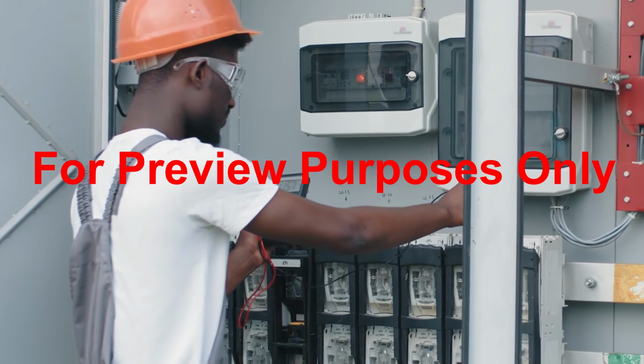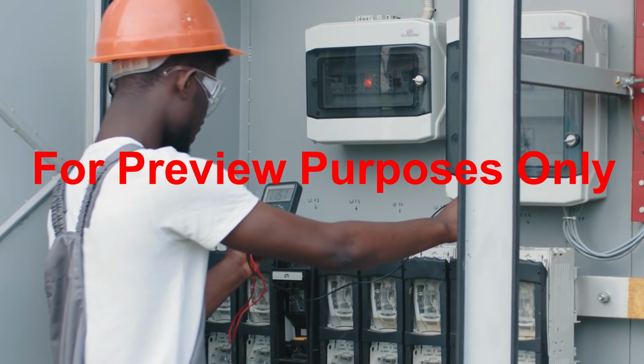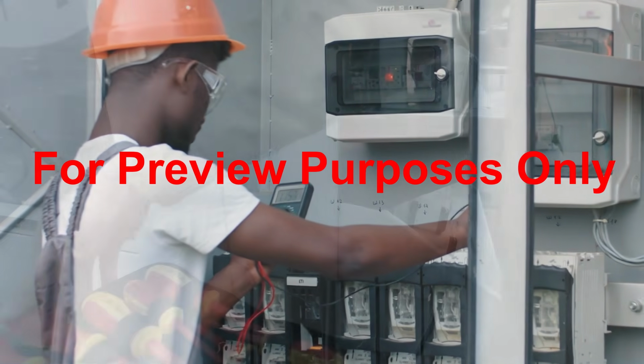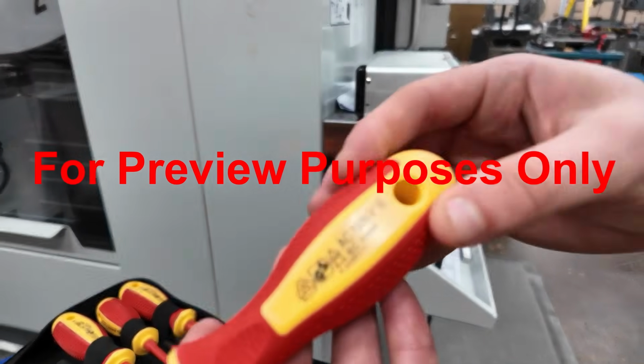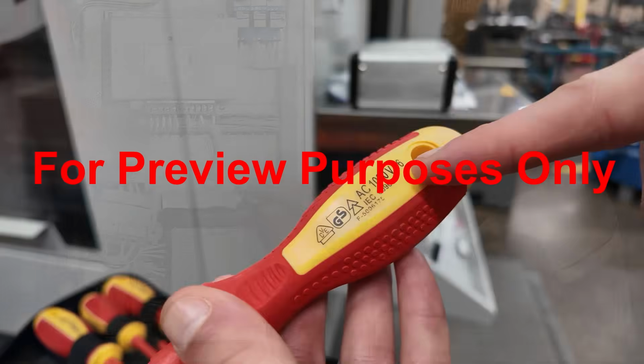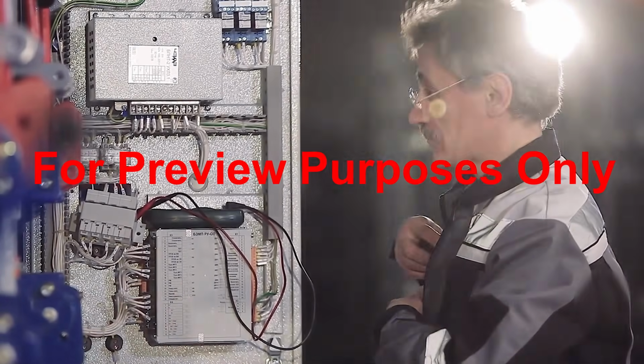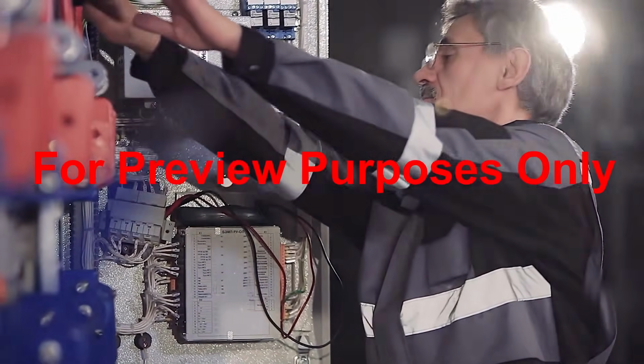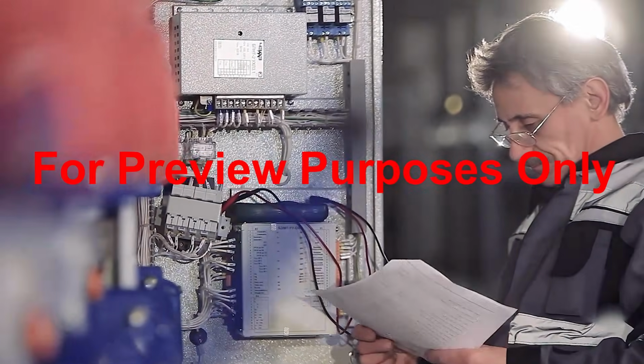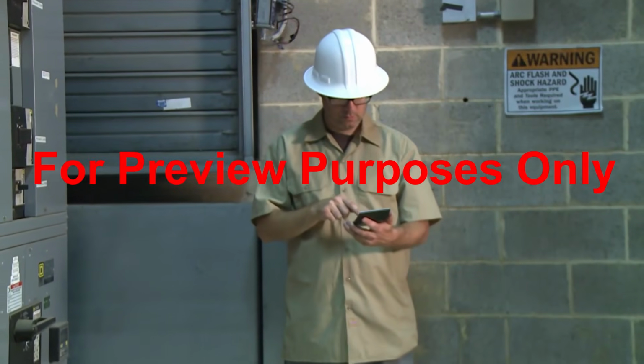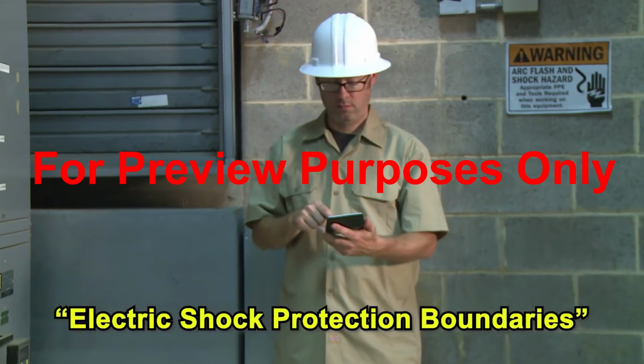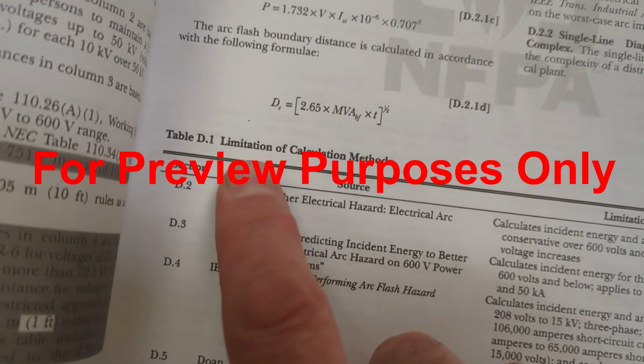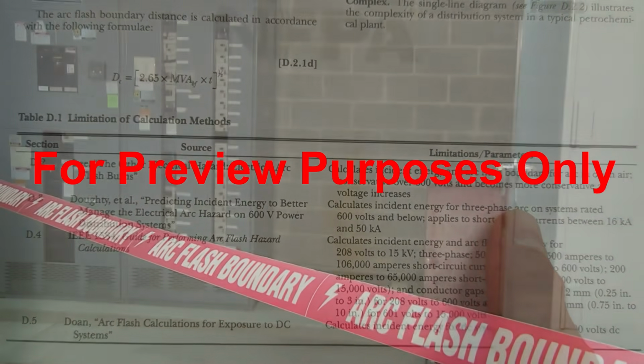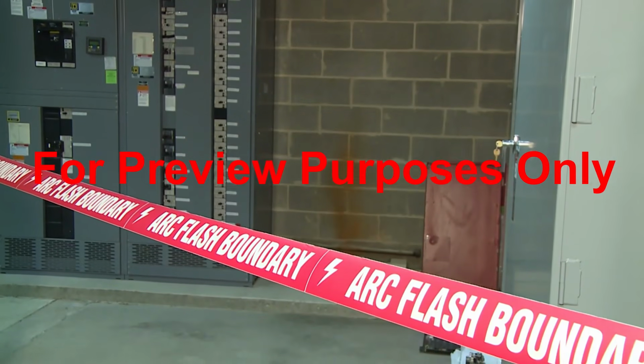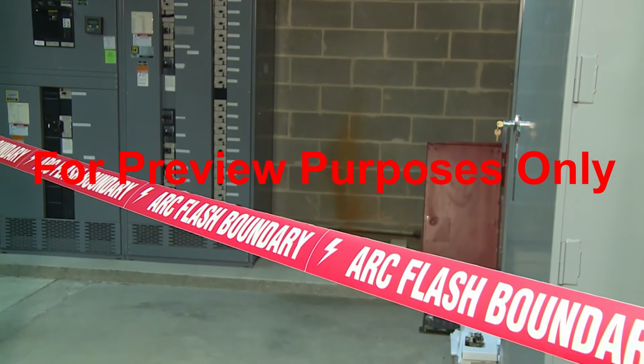During the assessment, you need to determine the voltage of all the conductors in your vicinity and the voltage ratings of the tools you're going to use. You should also consider the design of the equipment that you're working on and how well it has been maintained. These factors can help you calculate the electric shock protection boundaries using the table that the NFPA 70E standard provides. These boundaries should be marked using signs or other visual indicators.